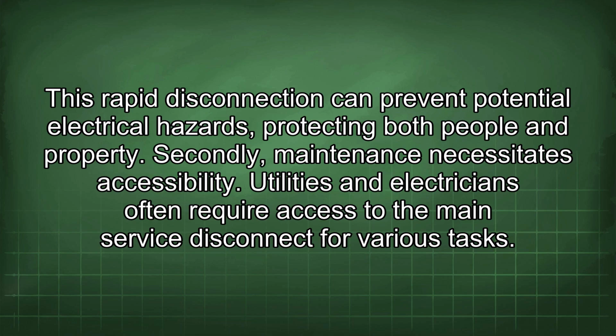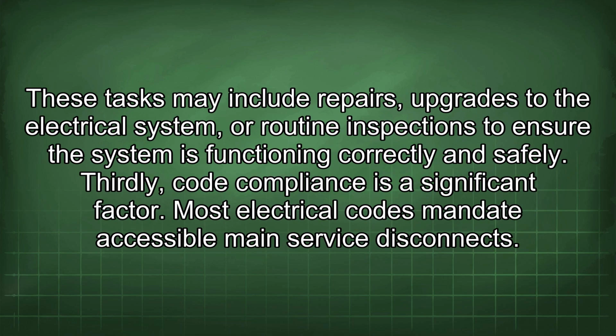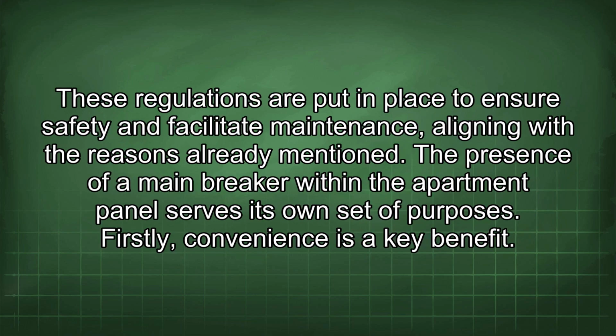Secondly, maintenance necessitates accessibility. Utilities and electricians often require access to the main service disconnect for various tasks. These tasks may include repairs, upgrades to the electrical system, or routine inspections to ensure the system is functioning correctly and safely. Thirdly, code compliance is a significant factor. Most electrical codes mandate accessible main service disconnects. These regulations are put in place to ensure safety and facilitate maintenance, aligning with the reasons already mentioned.